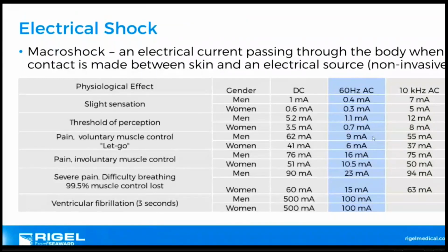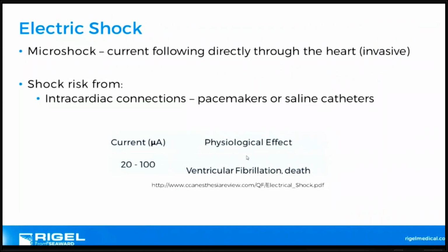thresholds almost. And a lot of electrical safety testing and dielectric strength testing sit there or thereabouts around these points. But what we've got is that the increase in frequency means it takes a lot more current to have the same physiological effect. And this is where things get a little important with low-pass filters and how the body reacts to current. And then we have a thing called microshock. Now, microshock is invasive, and it takes a lot less current to send the heart into ventricular fibrillation than it would non-invasively. This is an important part of electrical safety and understanding physiological effects.